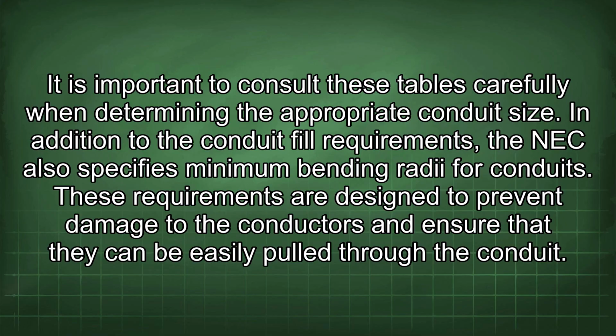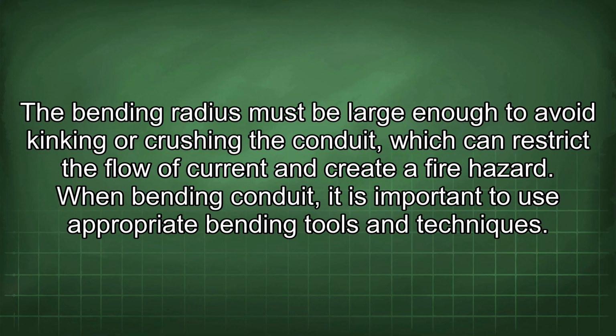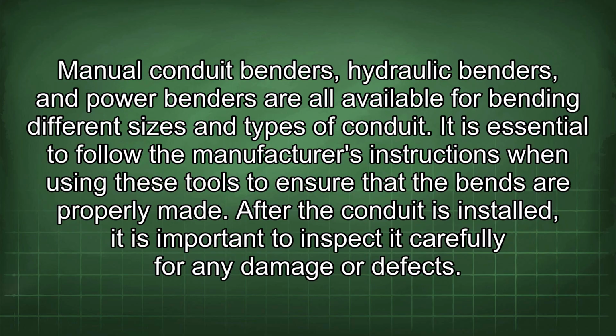In addition to the conduit fill requirements, the NEC also specifies minimum bending radii for conduits. These requirements are designed to prevent damage to the conductors and ensure that they can be easily pulled through the conduit. The bending radius must be large enough to avoid kinking or crushing the conduit, which can restrict the flow of current and create a fire hazard. When bending conduit, it is important to use appropriate bending tools and techniques. Manual conduit benders, hydraulic benders, and power benders are all available for bending different sizes and types of conduit. It is essential to follow the manufacturer's instructions when using these tools to ensure that the bends are properly made.